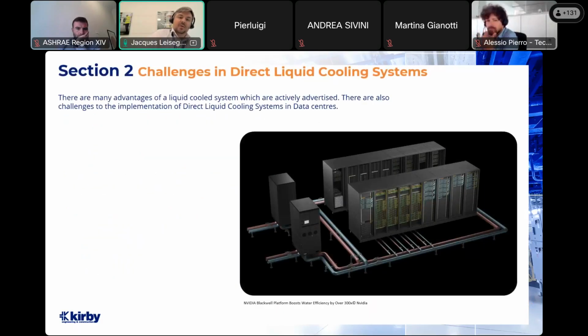All right, in the next section, we'll talk about some of the challenges associated with implementing direct liquid cooled systems. But I'm sure a lot of us have seen in the media, on the news, and advertised by a lot of the equipment vendors, all of the advantages associated with liquid cooled systems. They're actively advertised: better heat transfer capacity, increased densities, better energy efficiency and PUE. If you go with a liquid cooled system, you can generate heat for district heating applications. You get all these nice shiny brochures about how great liquid cooling is. This is a snip from NVIDIA saying this platform boosts water efficiency by over 300 times. So there's a lot of good advertisement going on about all the advantages of liquid cooling.